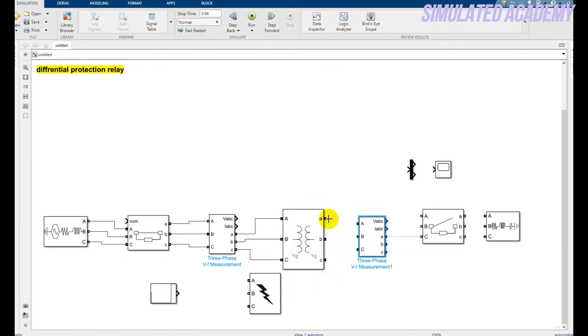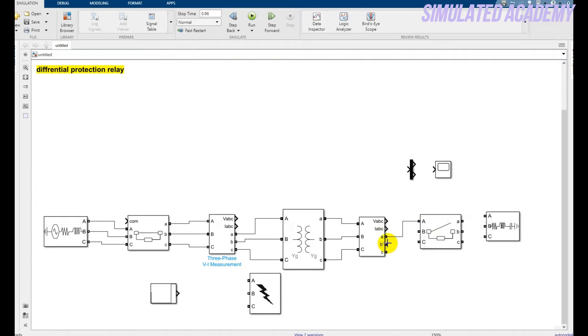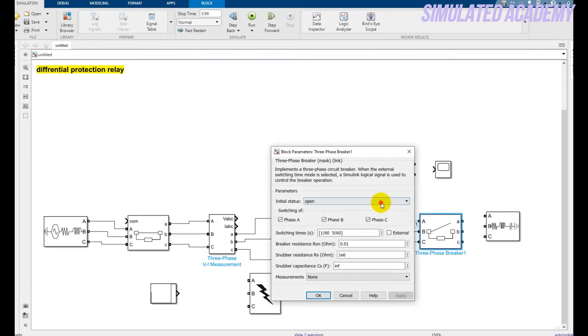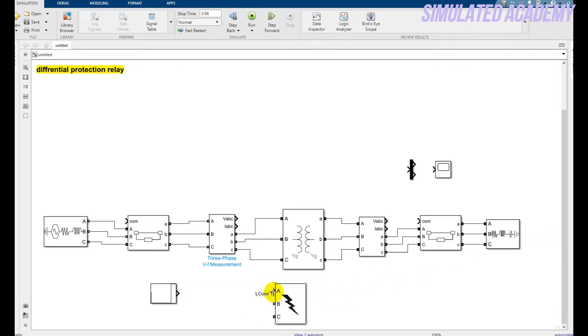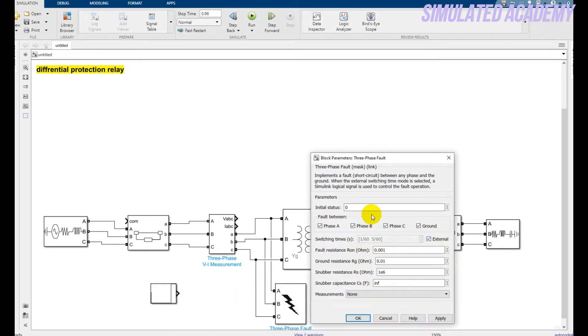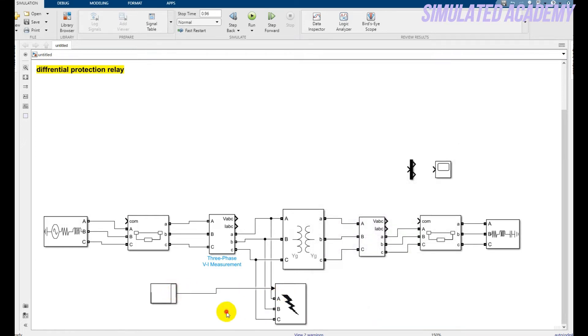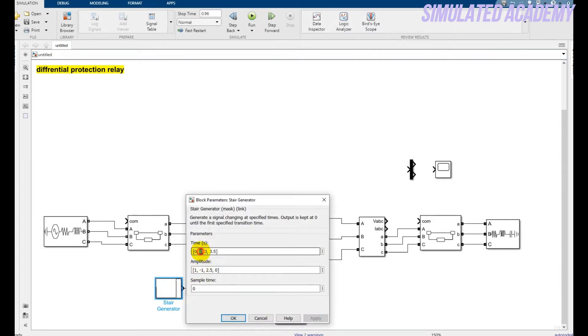Connect the secondary side with the VI three-phase measurement block. After that connect this with the voltage and current and the other breaker — double-click on it, initial state should be closed, fault should be external, click apply and OK. Now connect this with your load. Connect with the three-phase block to measure your voltage and current. Double-click on the fault block, change it to external, click OK, and connect the stair generator with it. Double-click on the stair generator and change some values: keep it 0.1, keep it 0.3, keep it 0.35, and the fault amplitude should be zero. Click apply, click OK.